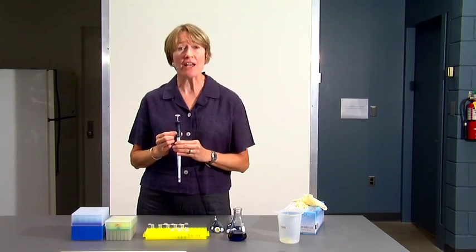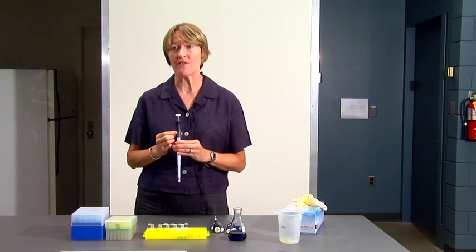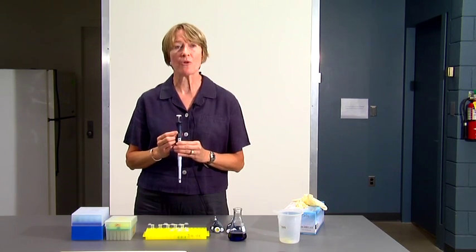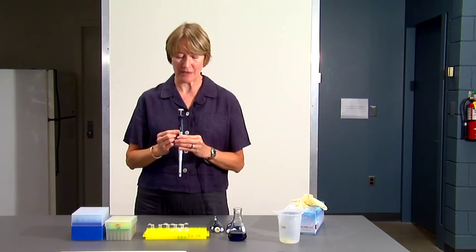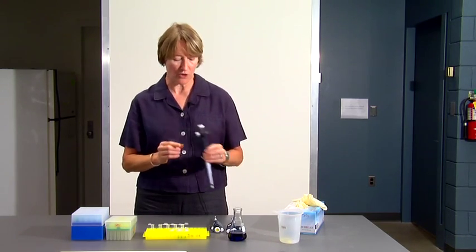If you wanted 500 microliters, that would be 050 on the P1000. So remember, the red number is thousands, and you have to make sure that you know how to set the pipet when you are setting your volume.